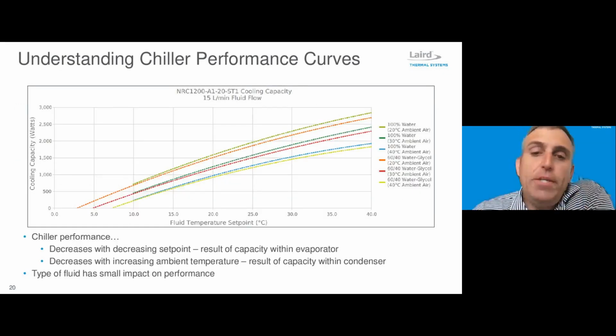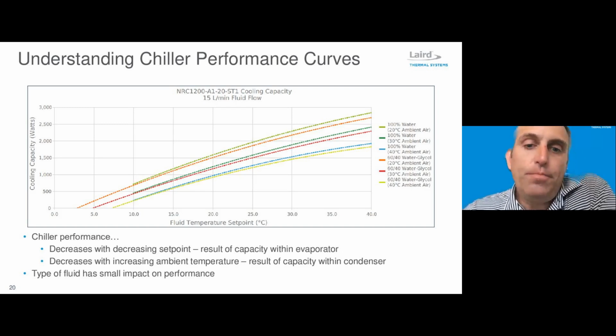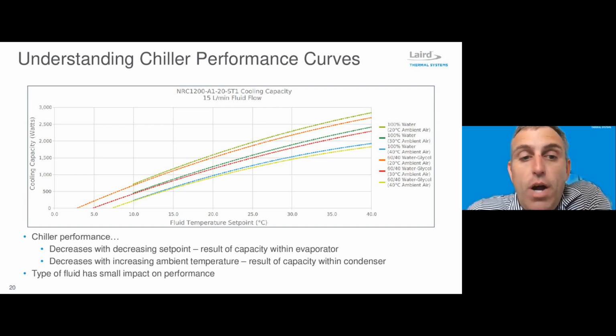And so if we take that information and look at what a typical cooling performance curve of a chiller looks like, we can begin the process of selecting that chiller. This chart shows the performance of Laird's NRC 1200 chiller. You can see on the y-axis the cooling capacity in watts. That is a function of the fluid temperature set point. As the fluid temperature set point is reduced, so is the cooling capacity.